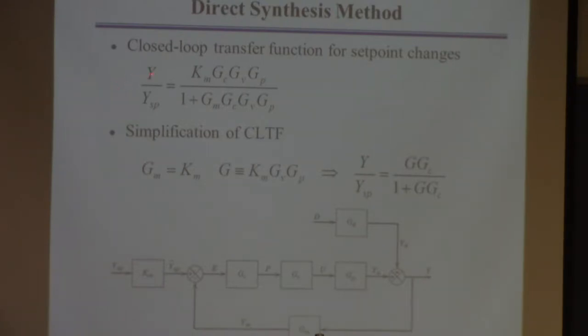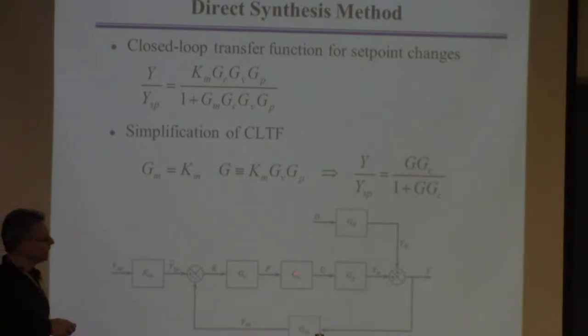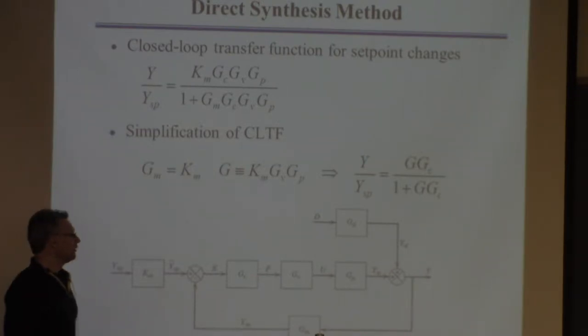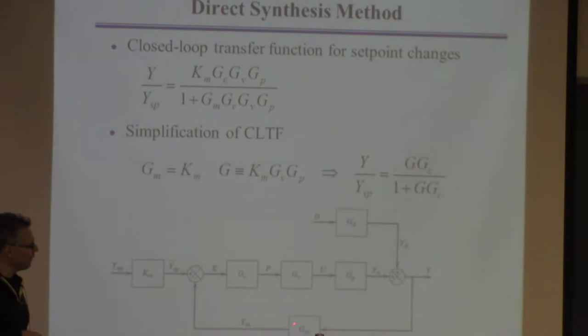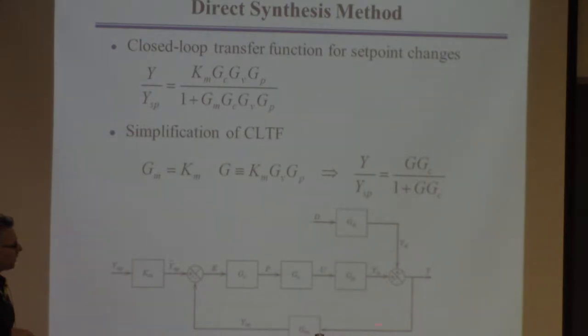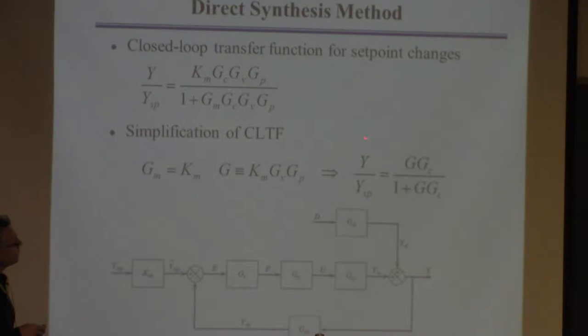Typically we have a transfer function that involves all these different elements. The point is: if you're in a plant, you can't tell the dynamics of the valve, the process, and the measurement apart from each other. You send a signal from the computer to the process, and out comes a measurement. You can't easily isolate the dynamics of the valve or the measurement device. So the way to think about it is: let's just call this whole thing the process — from here to here — because we can't tell the valve apart from the process, apart from the sensor.